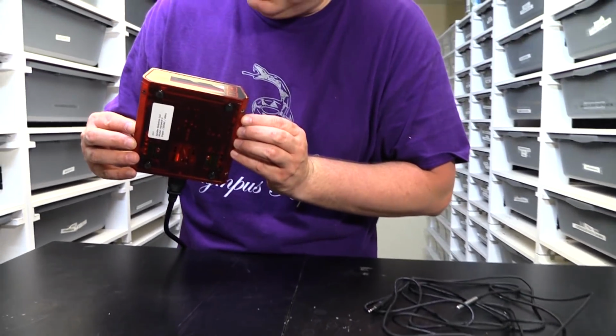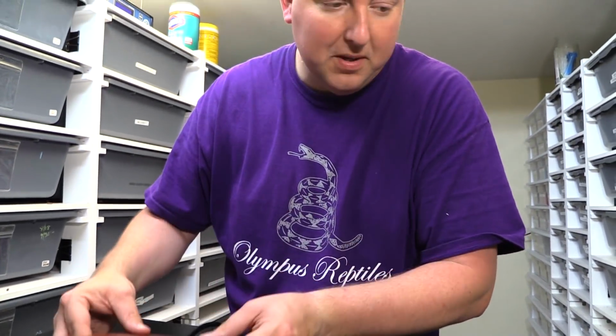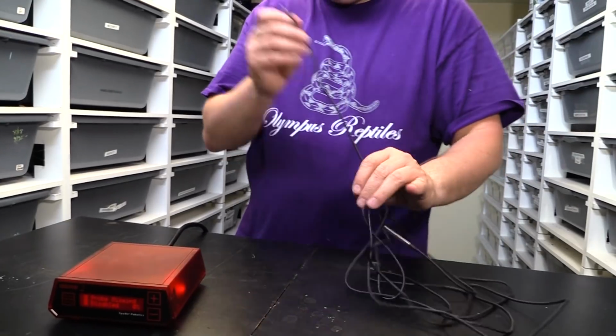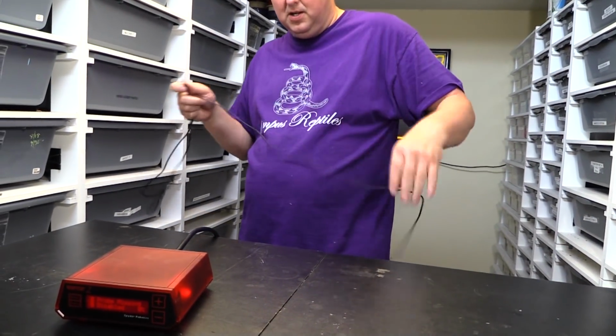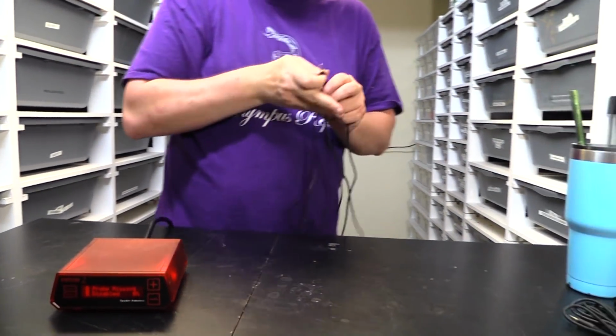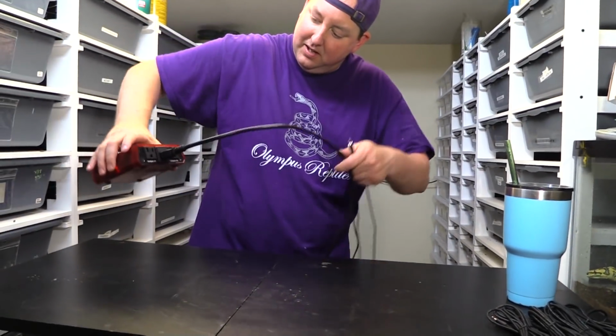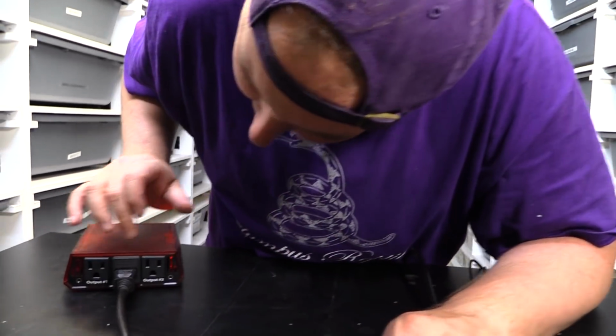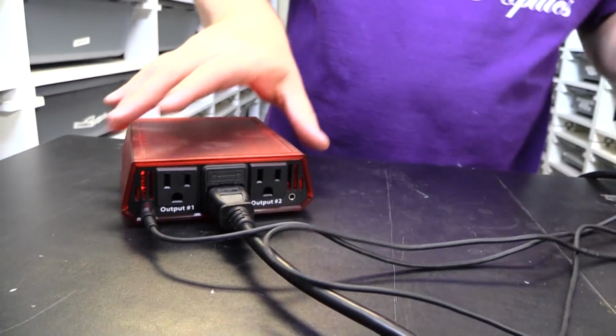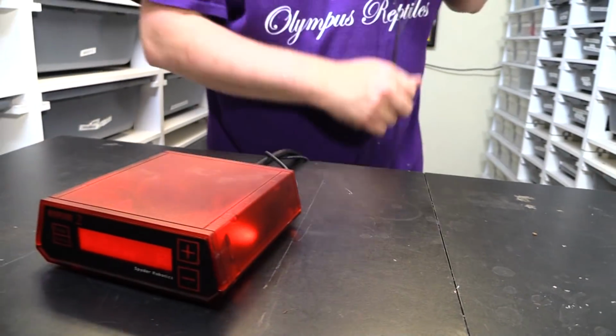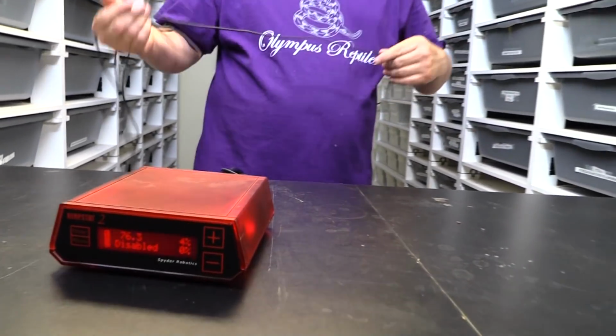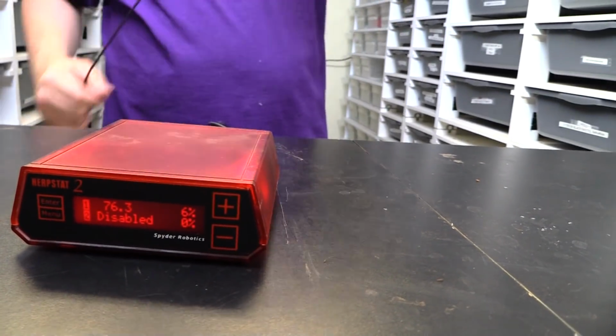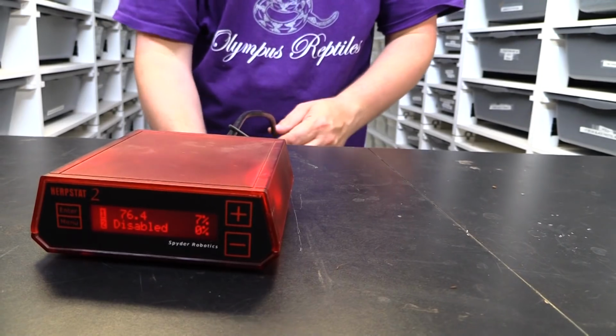Of course, it remembers the previous settings and says probe missing, then probe disabled. So if you wanted to put a probe in, say we're only going to use one output. On the back of this unit it'll say output 1, output 2. You just simply snap that into output 1. You can hear the beep stopped. And then what's it reading? 76.3. Cool, we'll warm that up here in a second.